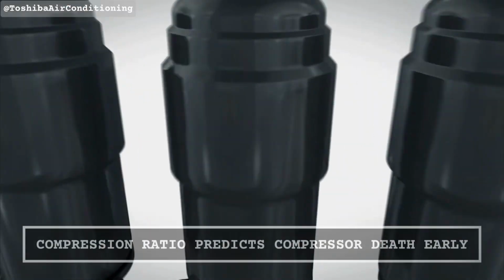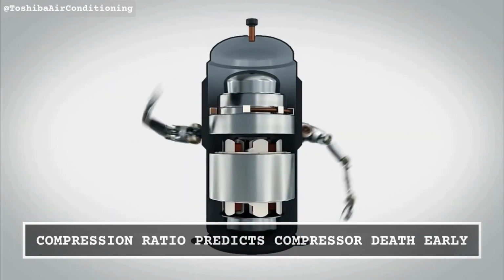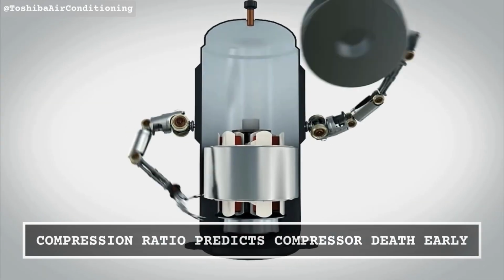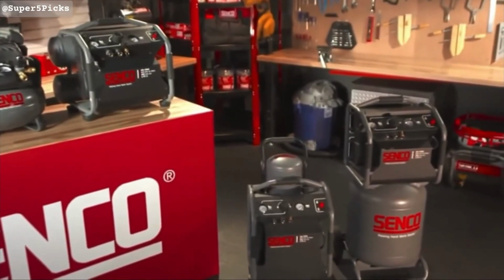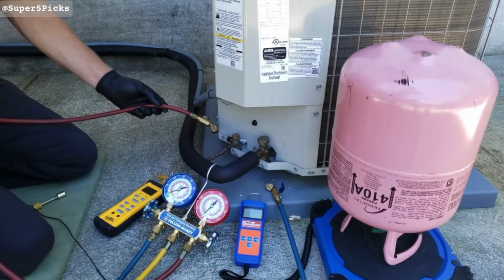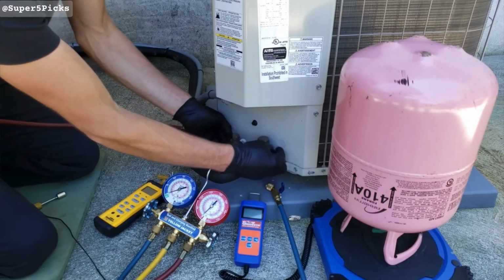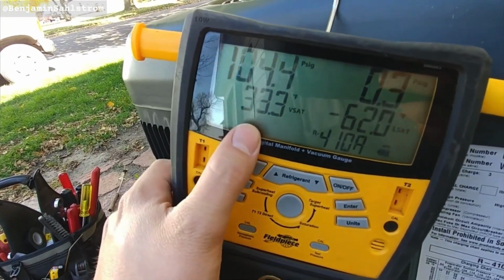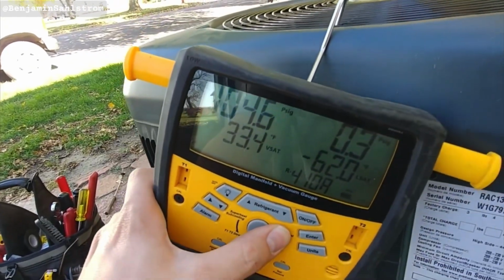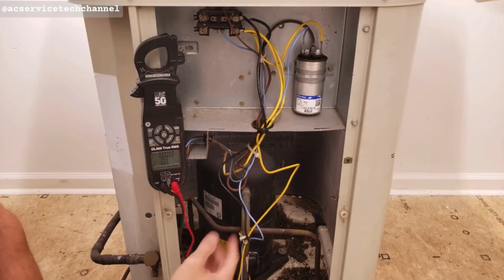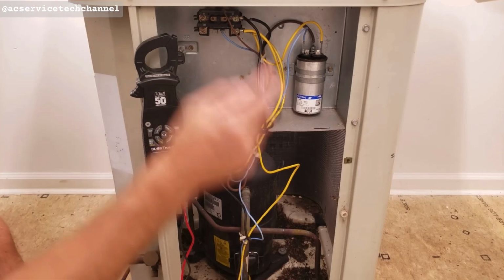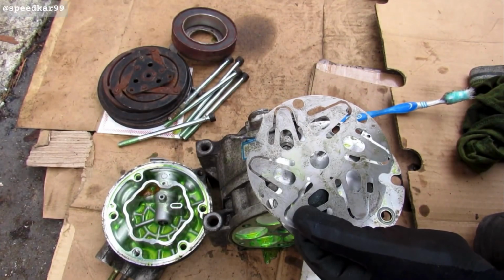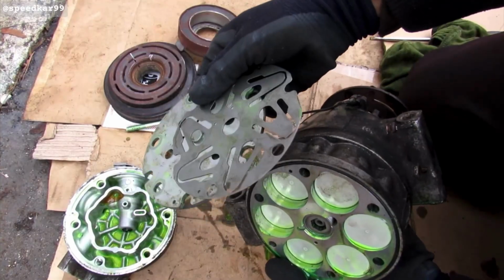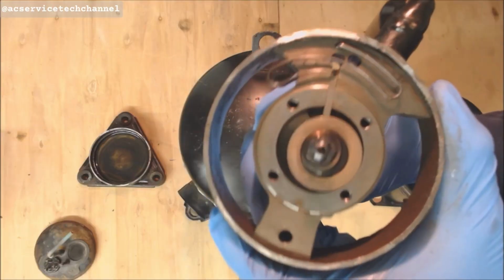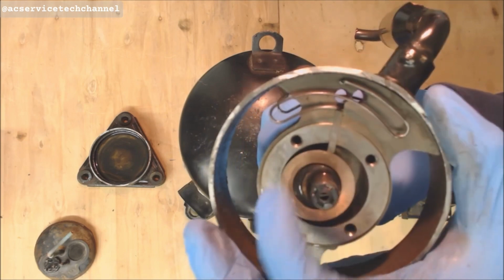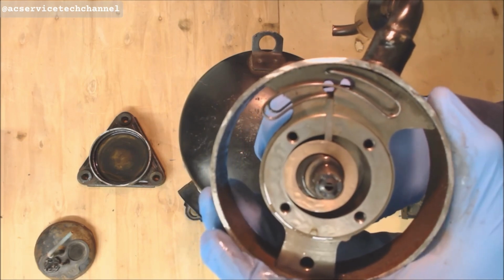Number 10. Compressor compression ratio is the diagnostic most techs never run. Compression ratio is the high side pressure divided by the low side pressure. On a healthy R410A cooling system at design conditions, you should see roughly 2.5 to 3.5. If the ratio climbs above 4:1 with clean coils, proper airflow, and correct charge, internal compressor wear is the most likely cause. It's the earliest sign that a compressor is on borrowed time, usually 6 to 12 months before the unit dies. Most homeowners replace systems 3 to 5 seasons too late because nobody was watching the ratio.